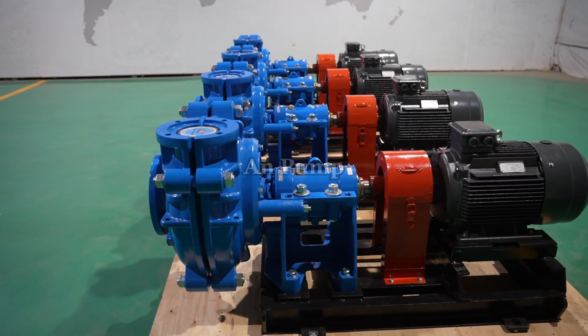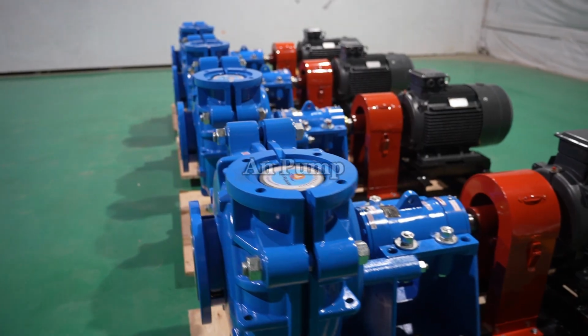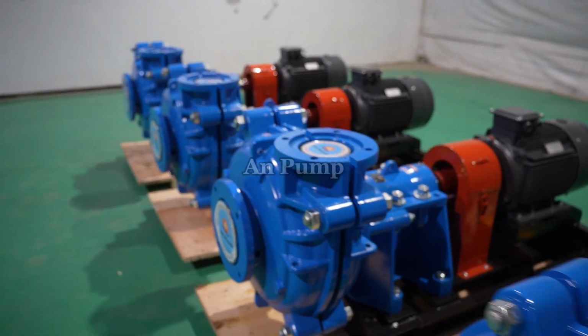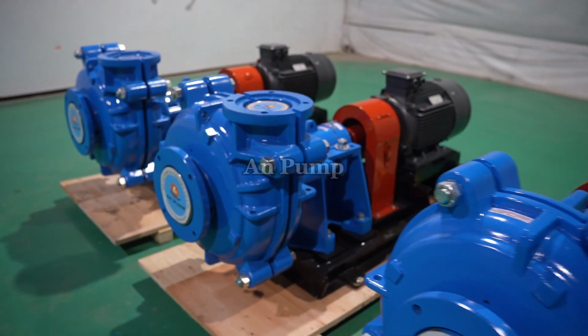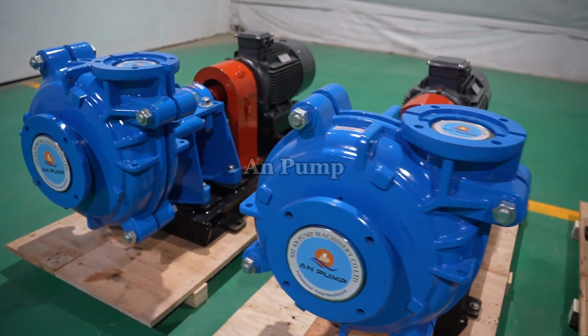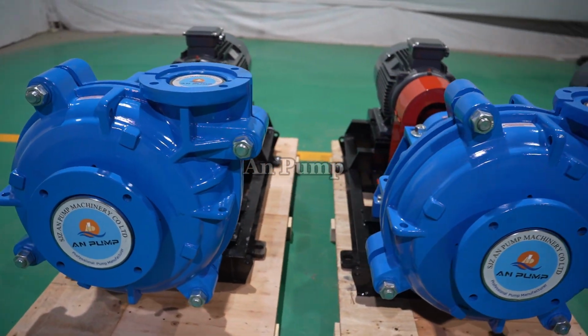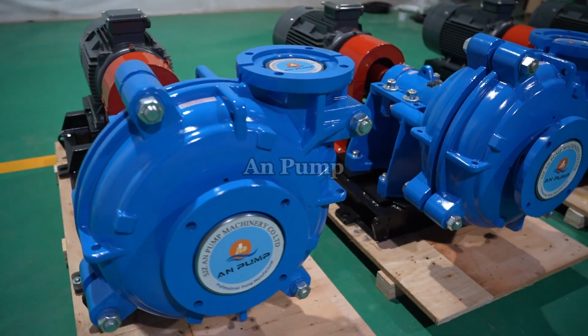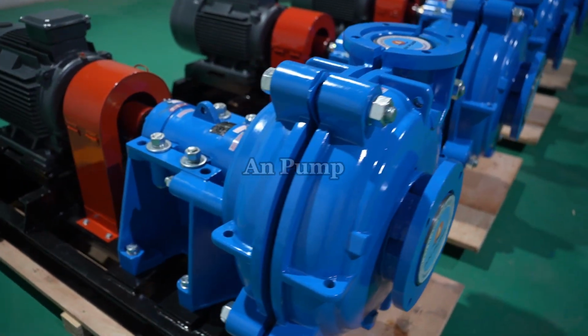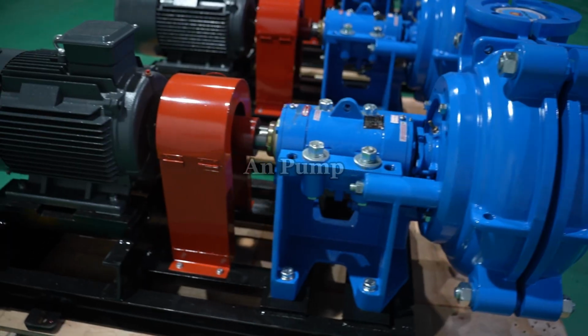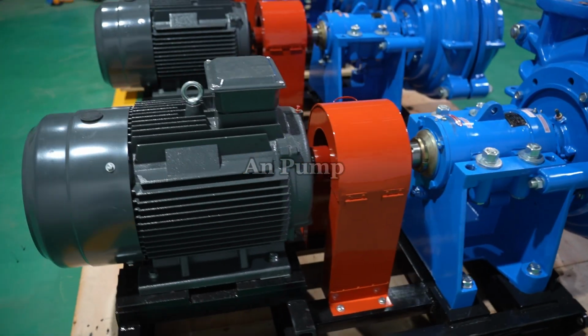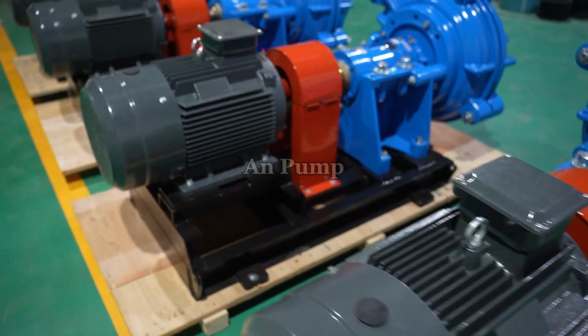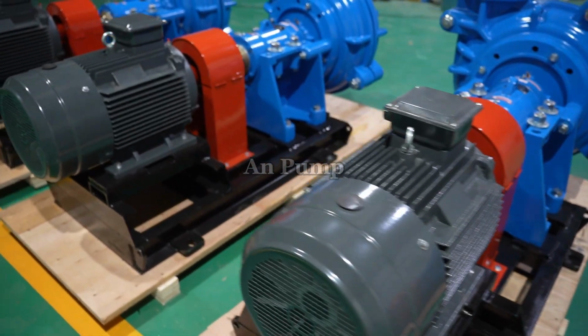Now let's talk about type number 4, the slurry centrifugal pump. Slurry pumps are a specialized category. They're engineered to handle fluids with suspended solid particles. If you try to run a standard centrifugal pump on slurry, it will fail quickly due to abrasive wear or clogging. A slurry pump has thick, replaceable liners, enlarged flow passages, and a rugged impeller.